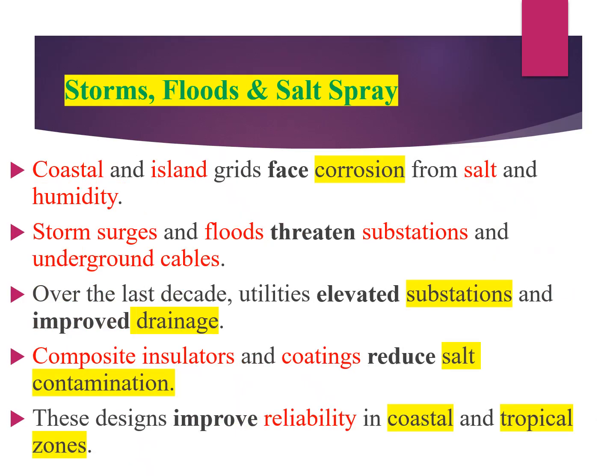Another interesting issue is the effect of storms, floods, and salt sprays on HV line systems. Coastal and island grids face corrosion from salt and humidity. Storm surges and floods threaten substations and underground cables. Over the last 10 years, utilities have elevated substations and improved drainage. Composite insulators and coatings reduce salt contamination, improving reliability in coastal and tropical zones.